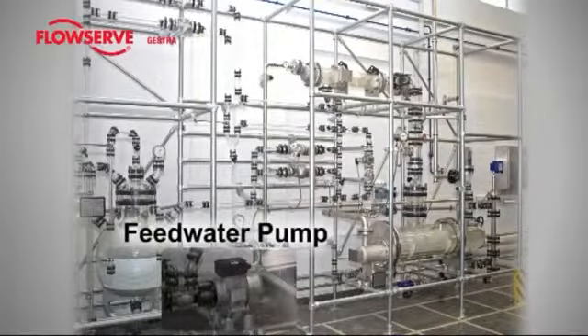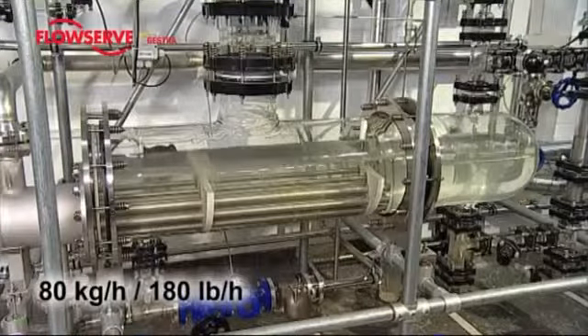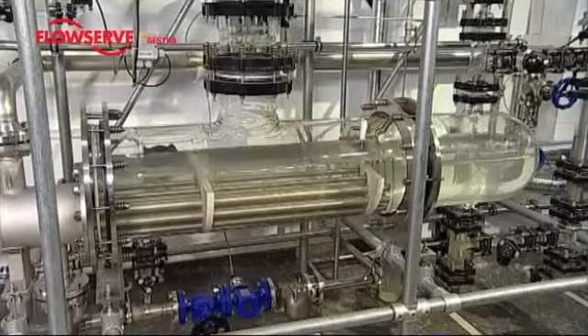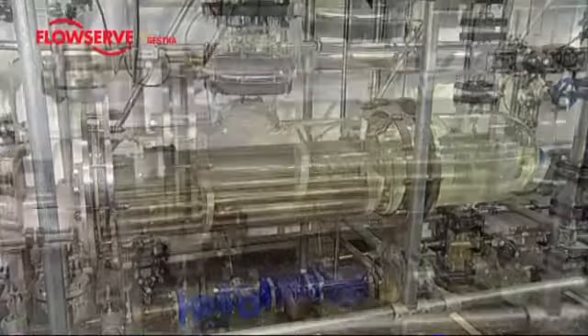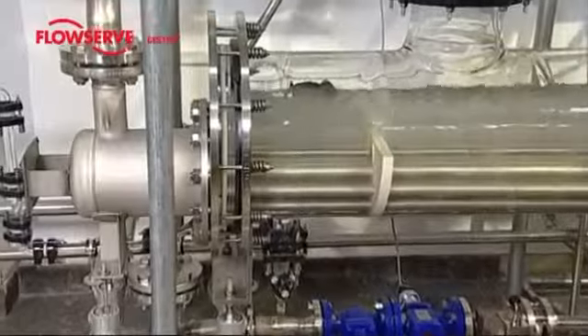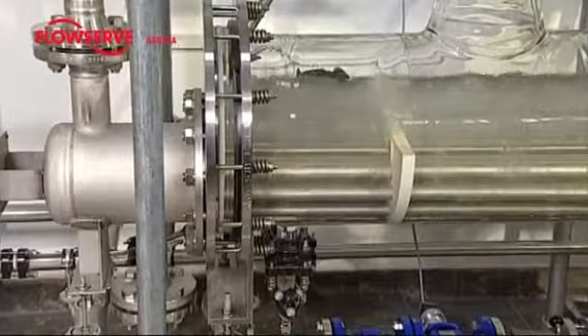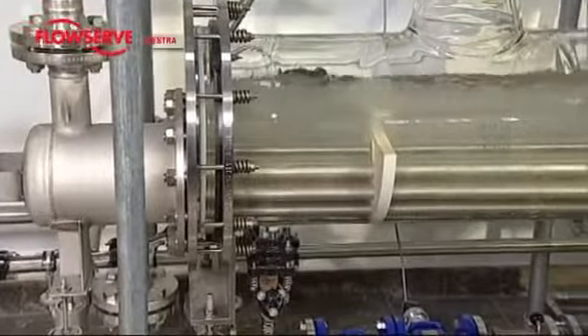The capacity of the steam boiler is 50 kilowatts, which yields a steam flow rate of 80 kilograms per hour. The steam generator consists of the following components: the horizontal evaporator with a stainless steel head for the primary steam inlet and condensate outlet, as well as 16 evaporator tubes, a pressure gauge with pressure transducer and a level measurement unit employing the capacitive measurement principle in an external measuring pot, a safety valve with a blow-off pressure of 1.5 bar gauge, and a steam outlet with a ball valve made of glass.